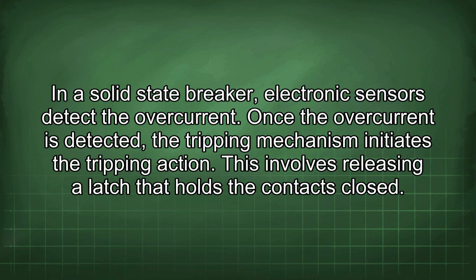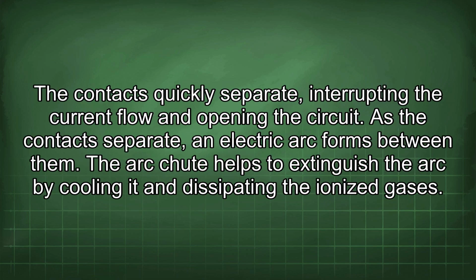Once the overcurrent is detected, the tripping mechanism initiates the tripping action. This involves releasing a latch that holds the contacts closed. The contacts quickly separate, interrupting the current flow and opening the circuit.